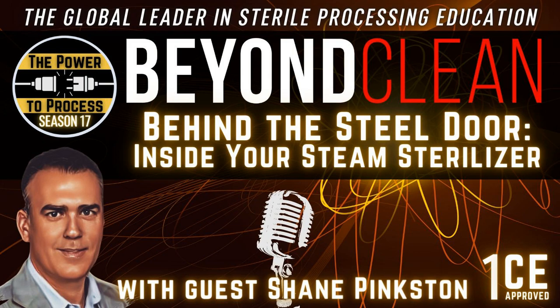The behind-the-wall part is where all the magic really does happen, Hank. That's where when you hit start or hit a button on the control panel, it's sending a signal to the control saying here's the program we have to execute. By doing that, it's telling the valves what to do. When you hear hissing and things like that, it's the pneumatics engaging on the valves to open or close, the steam coming into the chamber, water going down into the heat exchanger to collapse the steam that's coming out. We can't have temperatures over 140 degrees in the United States going down the drain — it won't meet code. So we have to quench that steam to collapse it as well.